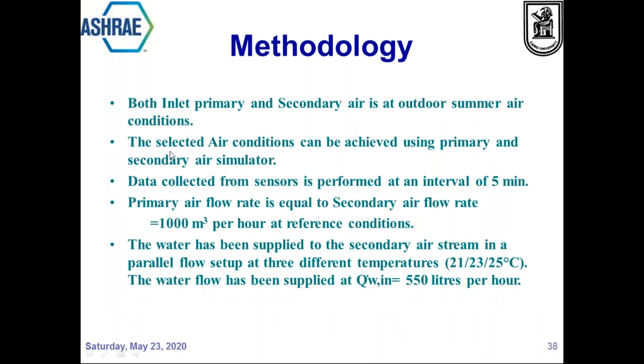In this methodology, both the inlet for the primary and secondary air are adjusted to outdoor summer air conditions in the city under investigation, whether it is Cairo, Sharm el-Sheikh, Dubai, any place in Dallas, or whatever. The selected air conditions are to be achieved by the primary and secondary air simulators. The data collected from the sensors is collected every 5 minutes. So we have a large number of data points in order to raise the level of confidence in the results.